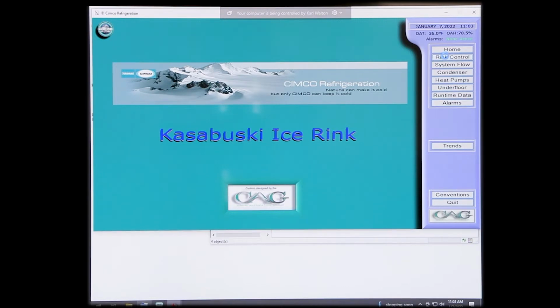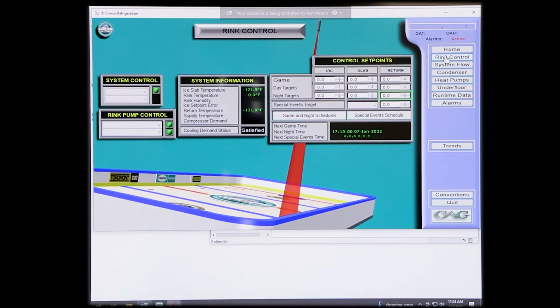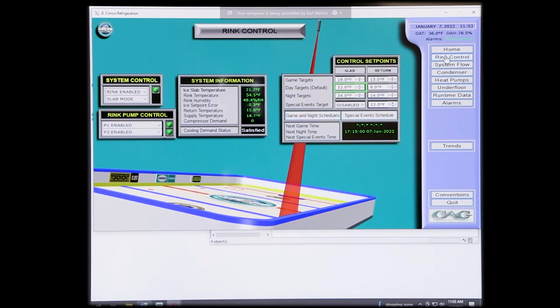Let's go to Rink Control. Within Rink Control, we have System Control in the upper left here. Rink Enable, Rink Disable. If you needed, for whatever reason, at end of season, just turn the rink off, this is where you would do it. You would literally come in here, hit Rink Disable, logged in under Supervisor, click that, and the whole package goes dark. Nothing starts. You will get no alarms. Nothing. It's lights out, put the key in the door, have a nice day.